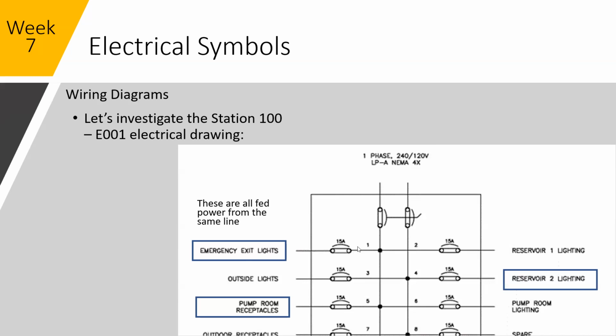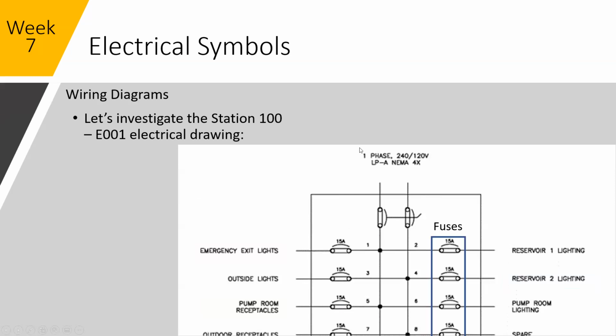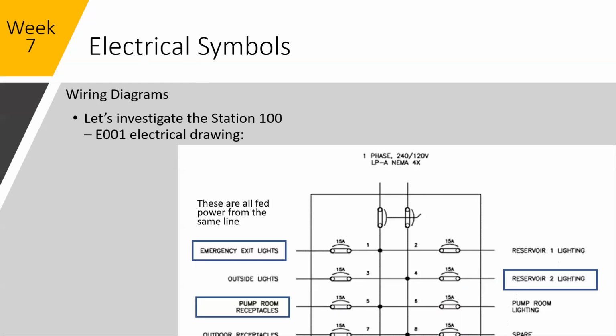Each one of these is 120. It's being broken into your 15 amp fuses where these dots are. I don't know why this box is here, because the way I read this drawing, call this A, L1 and L2. L1 is connected to 1 and 2. L1 is connected to 5 and 6. And L2 is connected to 3 and 4 and 7 and 8. So I read this that this is incorrect. So I would actually, yeah.